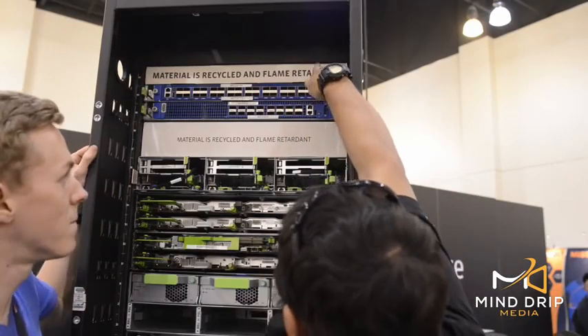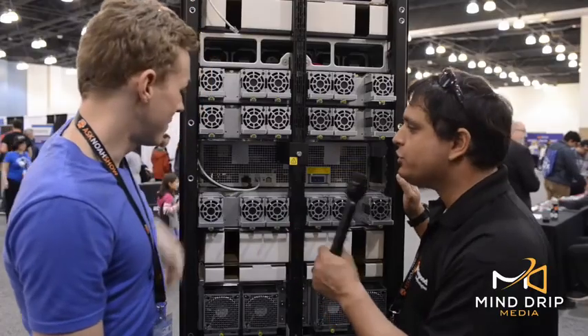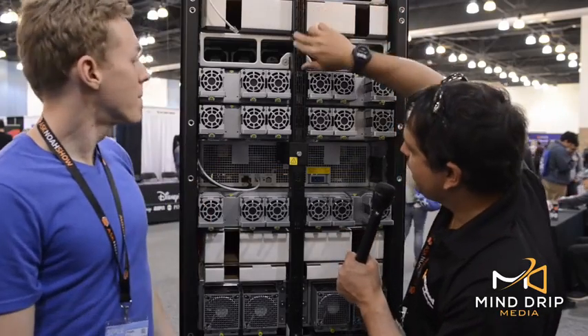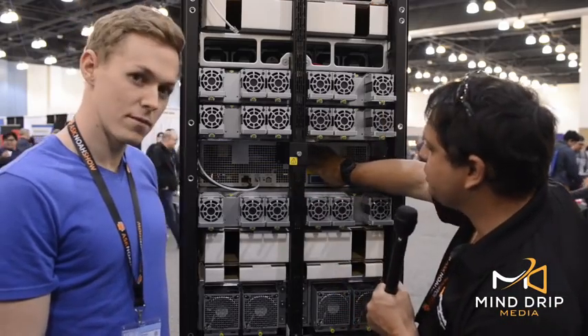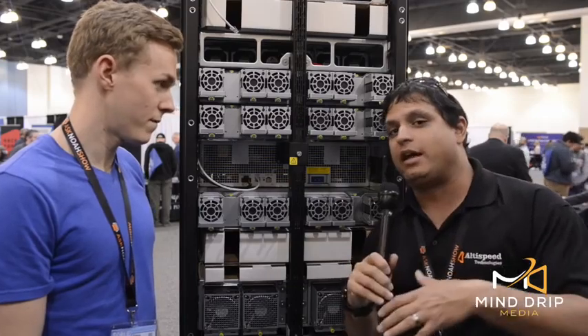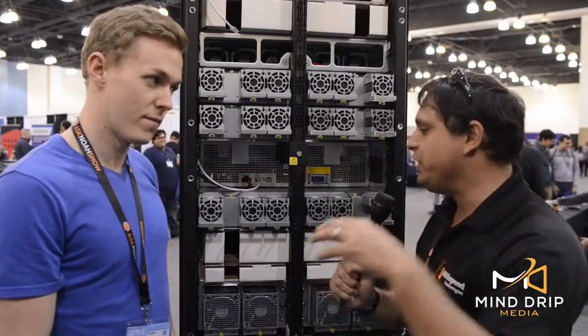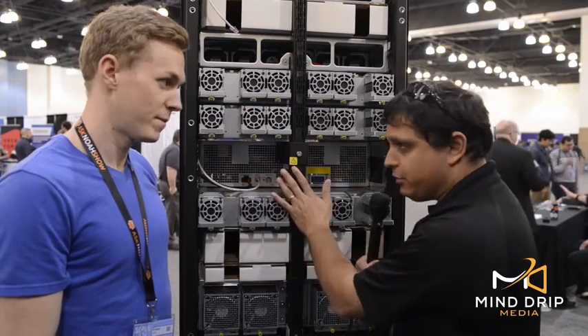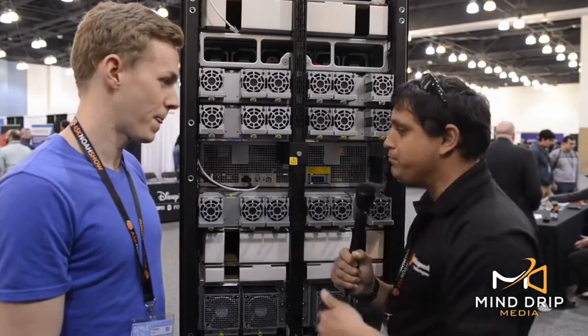The rack is a different dimension than your standard 19-inch rack — it's actually 21 inches wide. They've installed switches that are 19-inch compatible but have expanders to fit the 21-inch rack. The rack itself has a backplane with two silver bars providing 12-volt DC power to the entire rack. This power supply unit, which also contains battery backup for the UPS, supplies DC power to the rack, eliminating power inefficiencies — you're not converting from AC to DC to AC to DC as you get into the components.